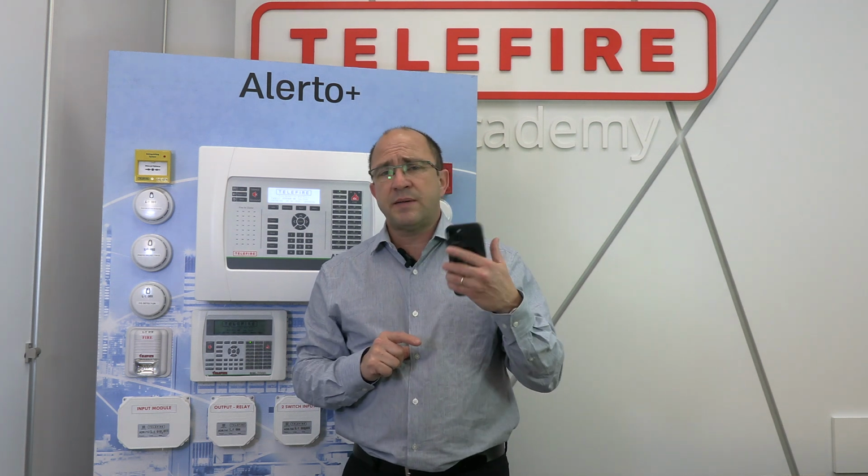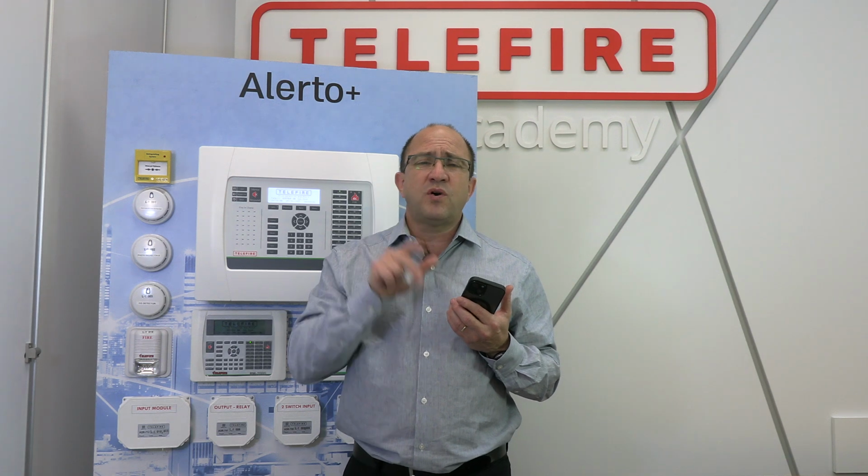After playing with that, we have again buzzer, silence of the whole system, disable. We can disable one of the devices or how many devices that I wish. We must just accept like a checkbox and say that I'm aware that I'm going to disable. That's the first time. Afterwards, he won't ask you anymore. And then reset. So we have 4 common things that we use every day.